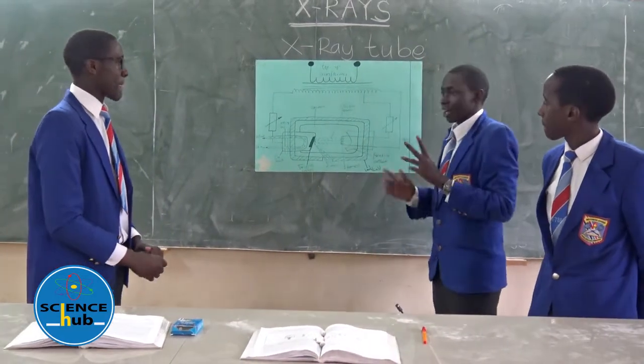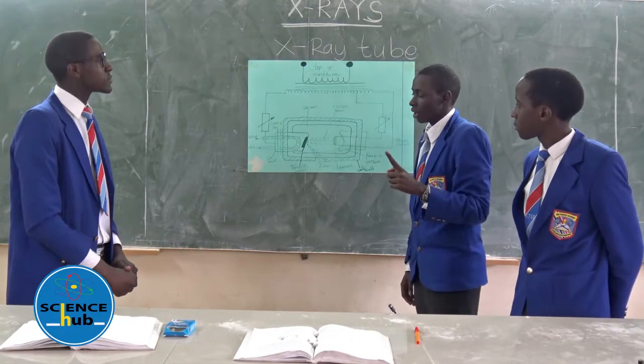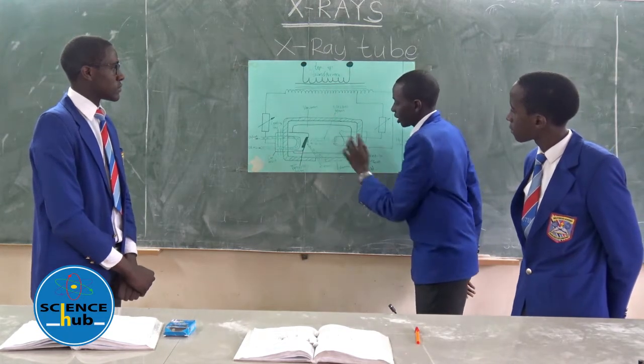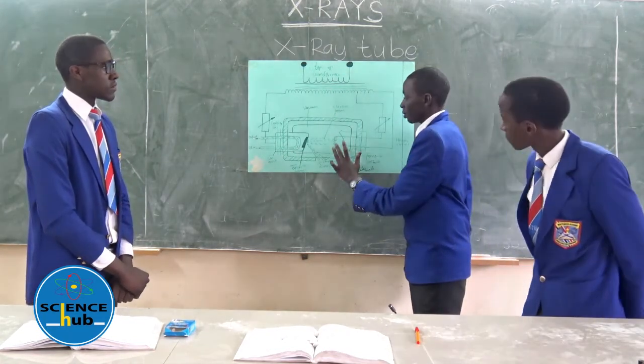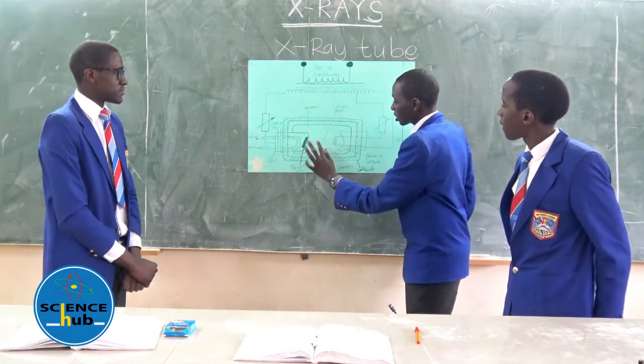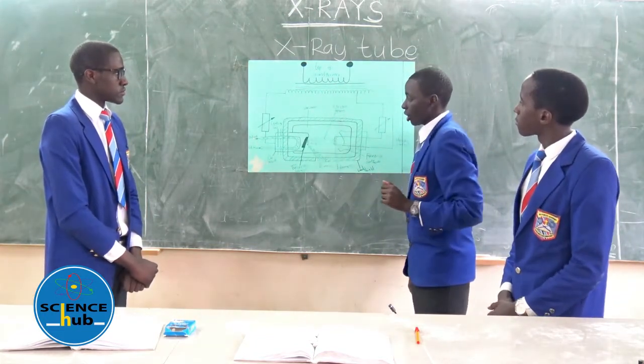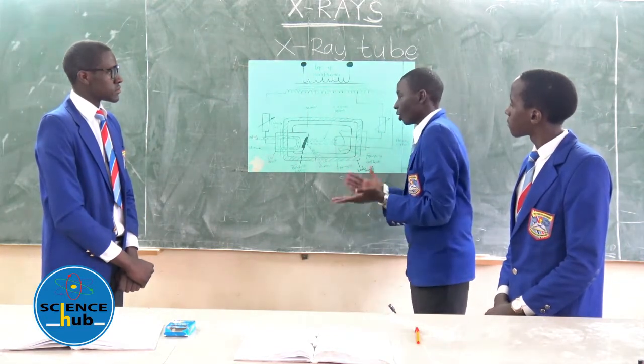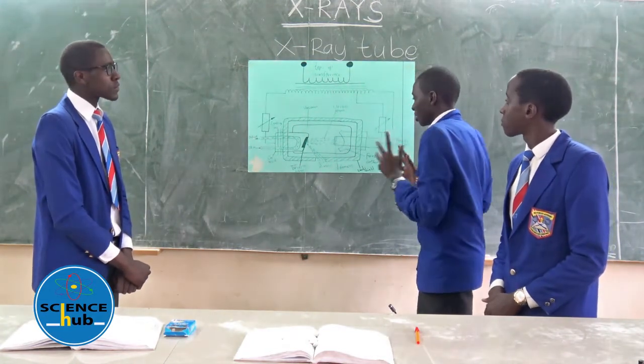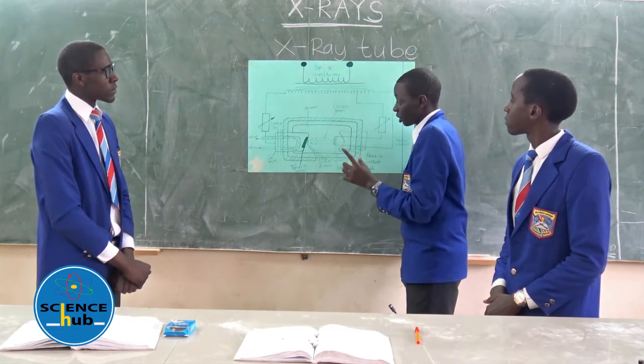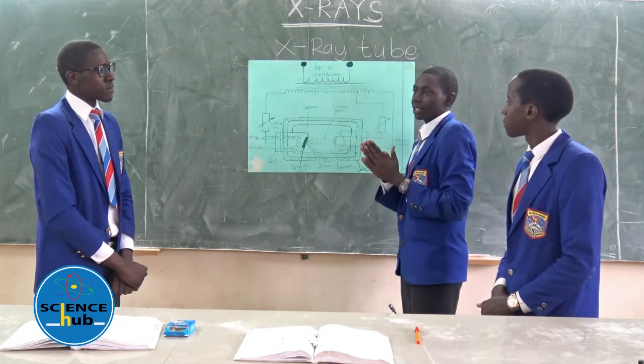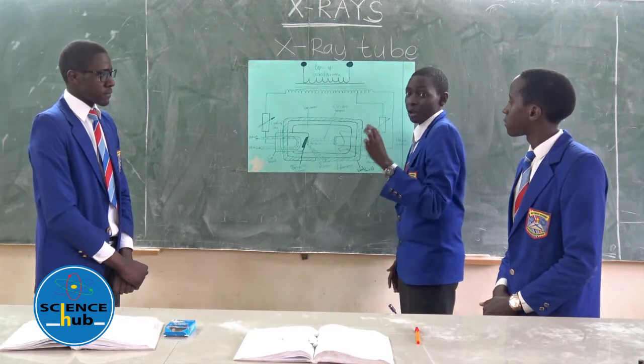The X-ray tube usually has two cycles: the first half cycle and the reverse half cycle. In the first half cycle, when the anode is positive and the cathode is negative, bombardment takes place — electrons hit the metal target and produce X-rays. But in the reverse half cycle, when the anode is negative and the cathode is positive, no bombardment takes place, so no X-rays are produced. Therefore, X-rays are produced in bursts.